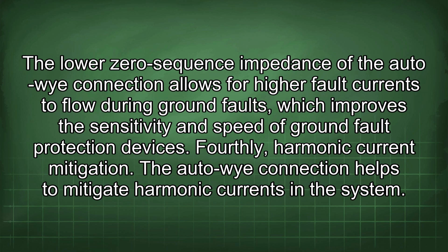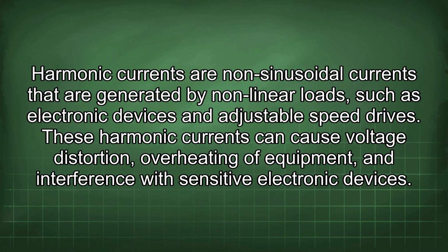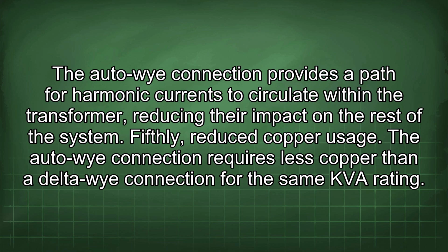Fourthly, harmonic current mitigation. The Auto-Wye connection helps to mitigate harmonic currents in the system. Harmonic currents are non-sinusoidal currents that are generated by nonlinear loads, such as electronic devices and adjustable speed drives. These harmonic currents can cause voltage distortion, overheating of equipment, and interference with sensitive electronic devices. The Auto-Wye connection provides a path for harmonic currents to circulate within the transformer, reducing their impact on the rest of the system. Fifthly, reduced copper usage. The Auto-Wye connection requires less copper than a Delta-Wye connection for the same kVA rating.